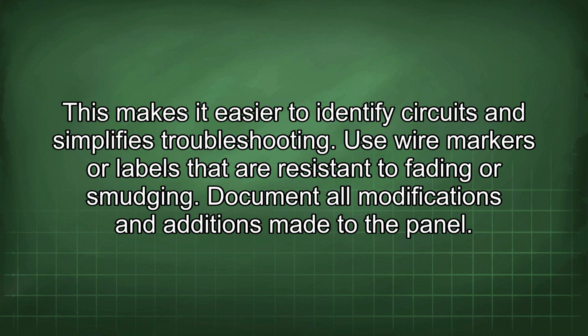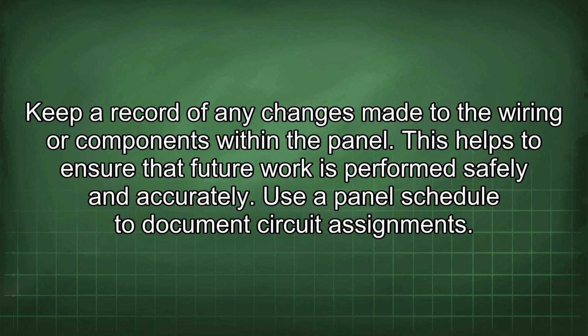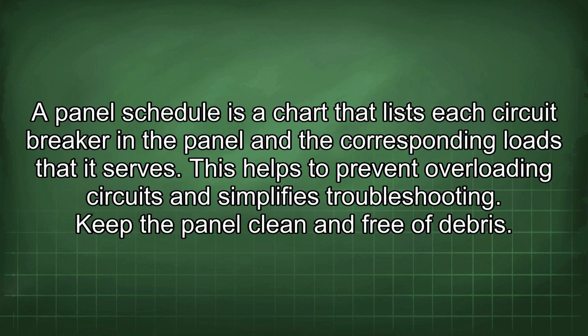Document all modifications and additions made to the panel. Keep a record of any changes made to the wiring or components within the panel. This helps to ensure that future work is performed safely and accurately. Use a panel schedule to document circuit assignments. A panel schedule is a chart that lists each circuit breaker in the panel and the corresponding loads that it serves. This helps to prevent overloading circuits and simplifies troubleshooting.